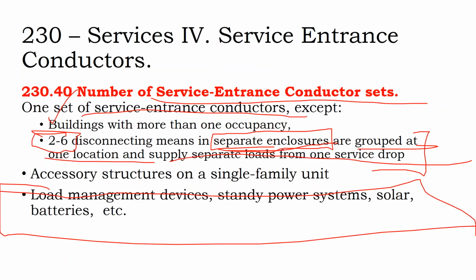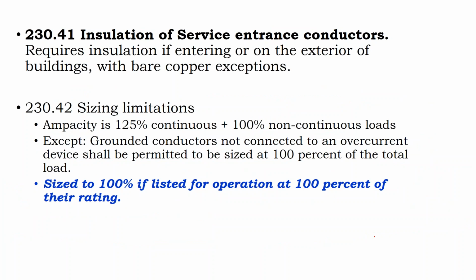And maybe there might be even additional situations where, if your jurisdiction allows you to have load management devices being different than emergency backup devices, you could have 18 disconnect switches, although most jurisdictions would say that would be a pretty messy design.